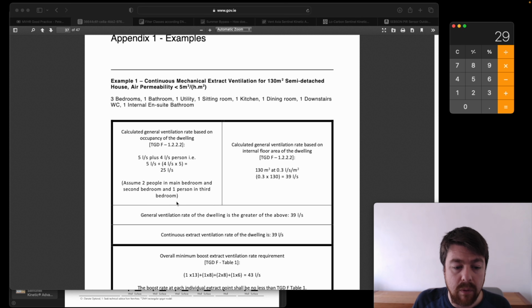Okay, but then what the building regs tell you to do is to calculate it in a different way and then take the worst case scenario. So we've got 29 calculated one way. Let's copy that. The house is basically a finished floor area of 122 square meters by 0.3 litres per second per square meter. So that comes up to 36. So that's obviously the worst case scenario. So let's take that as our working number, and we need to achieve basically 36.6 litres per second.